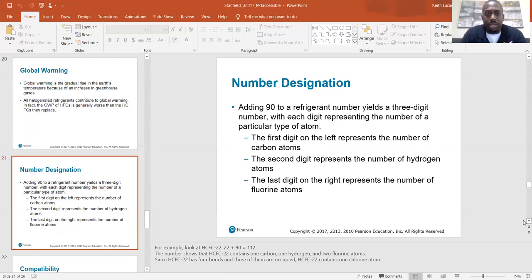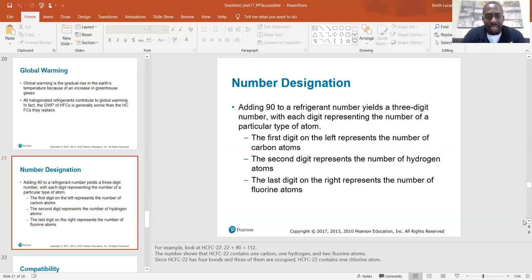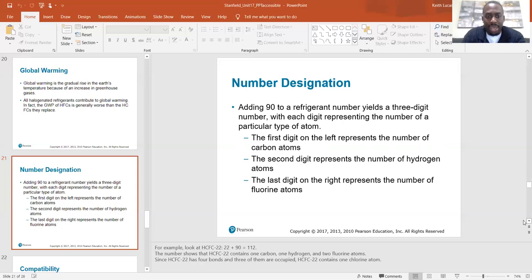Number designation: adding 90 to a refrigerant number yields a three-digit number, with each digit representing the number of a particular type of atom. The first digit represents the number of carbon atoms, the second represents hydrogen atoms, and the last represents fluorine atoms. For example, HCFC-22: 22 plus 90 is 112, showing that HCFC-22 contains one carbon, one hydrogen, and two fluorine atoms. Since HCFC-22 has four bonds and three are occupied, it contains one chlorine atom.